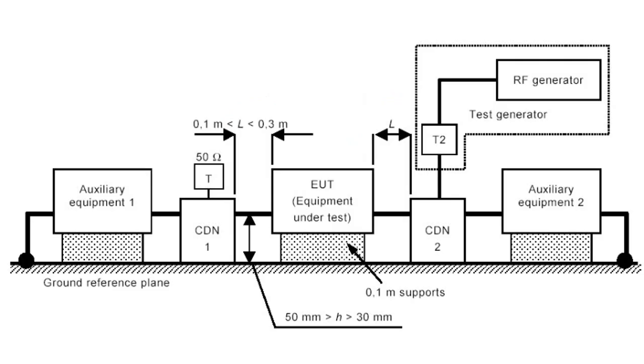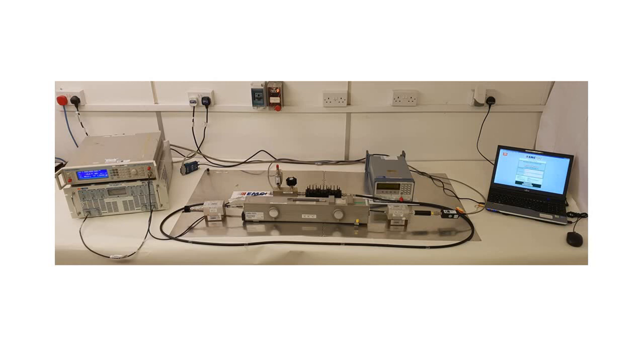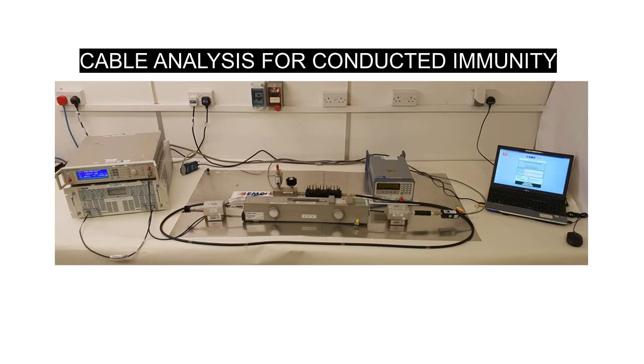Conducted immunity: at frequencies up to the point at which the EUT dimensions approach a quarter wavelength, the major coupling route into the EUT is via interference injected in common mode on the connected cables. Analyzing cables as a source is therefore an important method for checking RF susceptibility.